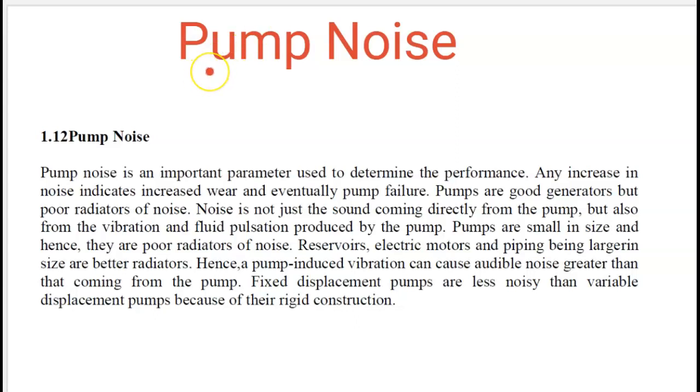Now, if we have a look at the other characteristic, which is pump noise, it's an important parameter used to determine the performance. Any increase in the noise indicates if there is any wear and tear, any failure of the pump, or any loss of energy. Pumps are good generators, but they are poor radiators of noise. Noise is not just the sound coming directly from the pump, but also from the vibration and the fluid pulsation produced by the pump.